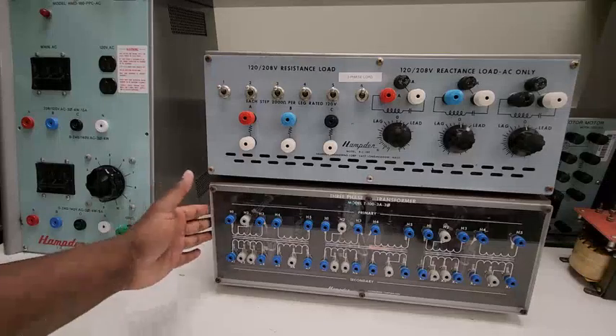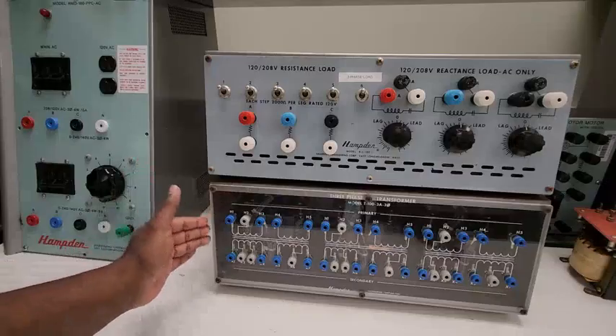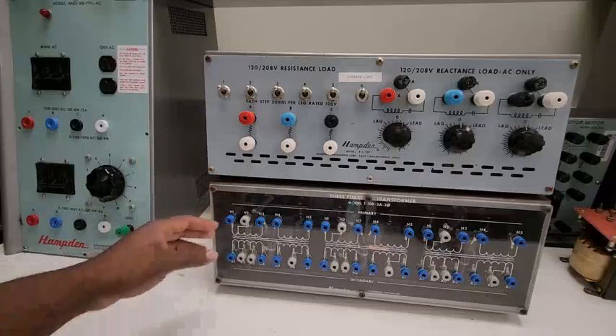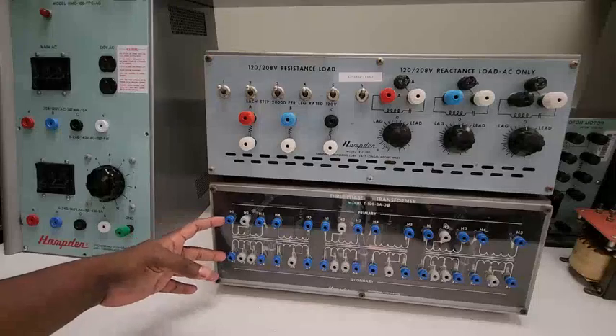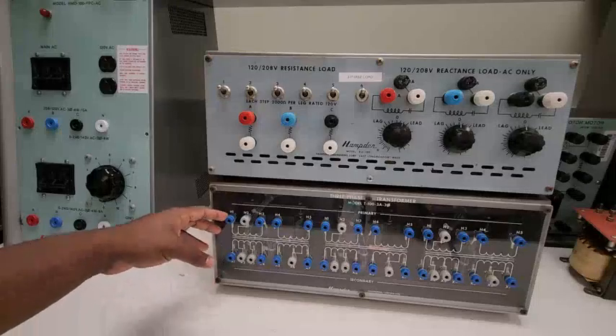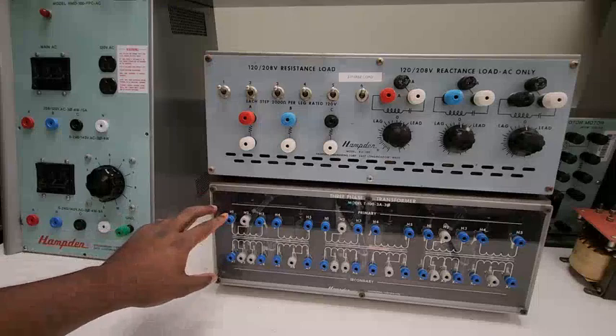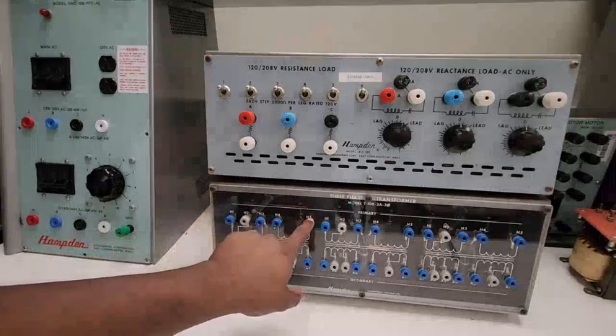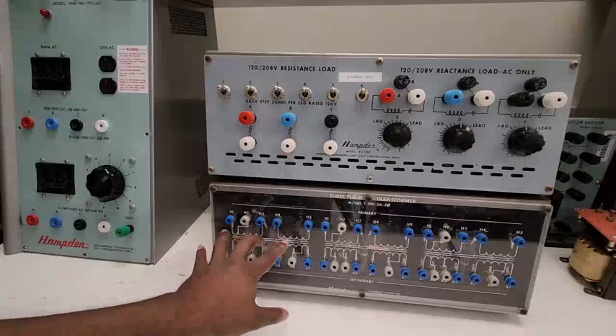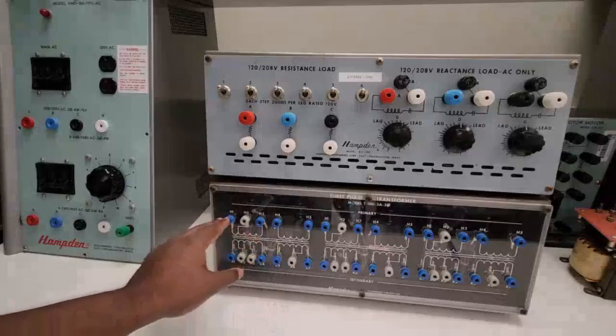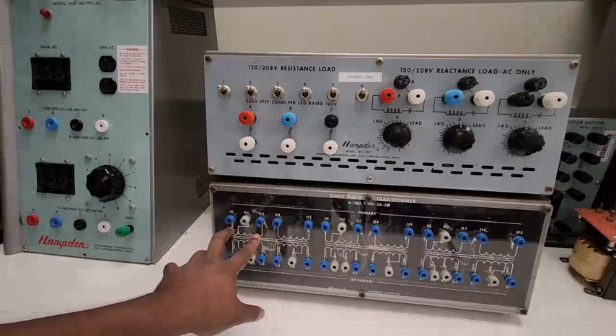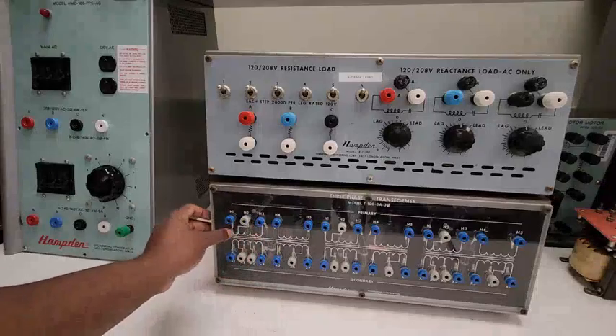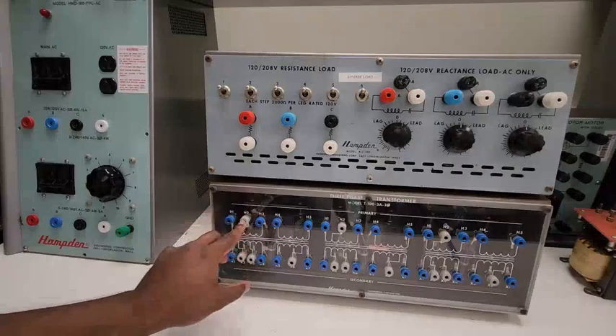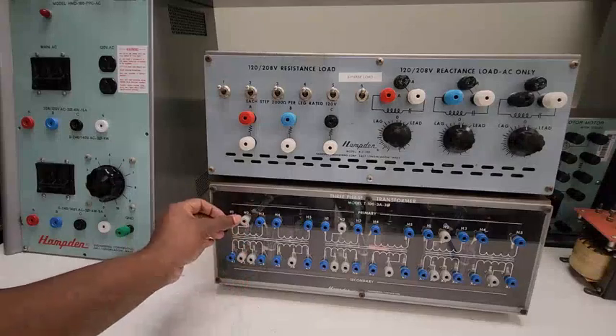Let's go to the transformer section. There are two segments, where in one we have the primary side, starting from H1 to H5. There are two separate windings: H1 and H3 is one winding, and we tapped out from H1 to form H2.